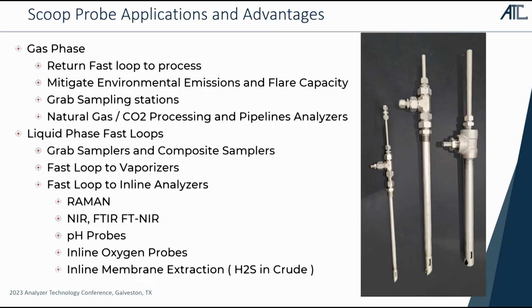So I'm wrapping up here right away. Scoop probe applications and advantages. In the gas phase, they can return a fast loop directly to, and I should have probably put in, a high pressure process. So we can mitigate environmental emissions and flare emissions. We don't have as much environmental emissions, we have less flow going to the flare lines. We can use the same thing for grab sampling stations like composite samplers. So in natural gas and CO2 pipeline analyzers, we can make sure that all of our fast loops are returned to the process. We don't have environmental, greenhouse gas emissions.